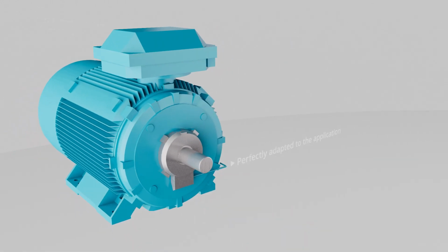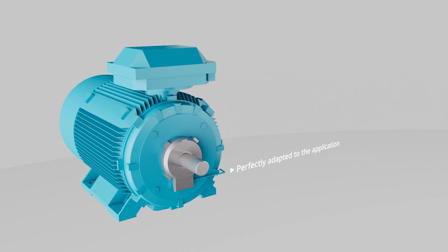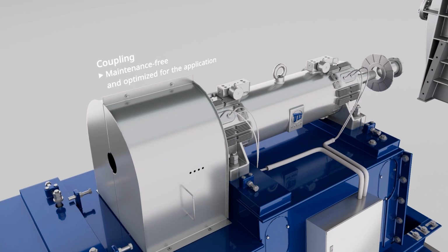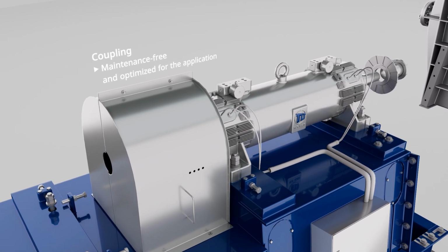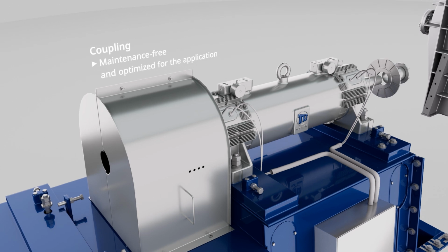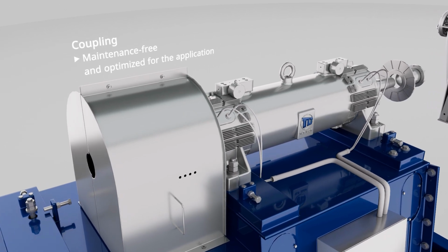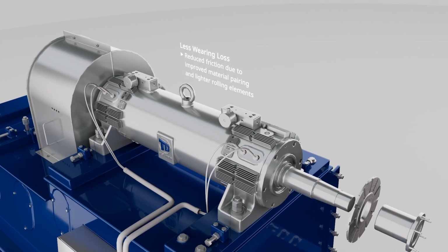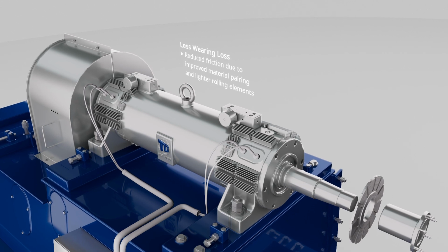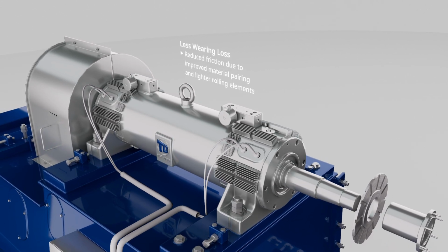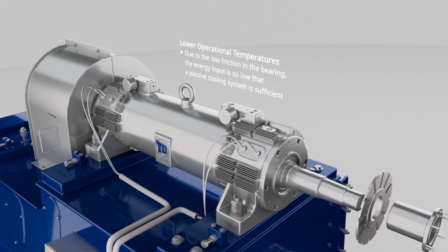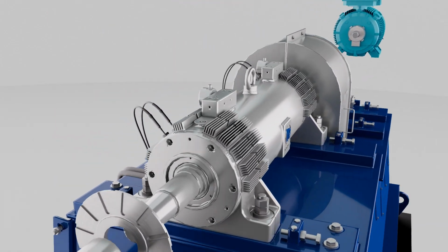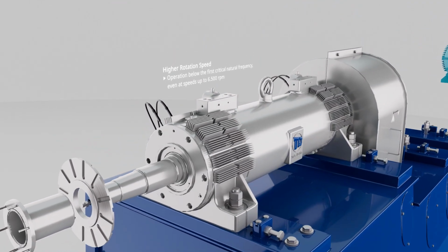One key component of the solution TLT Turbo developed is the practically maintenance-free bearing assembly. The assembly incorporates heavy-duty ceramic hybrid bearings, which has several benefits over conventional bearings in this application. Because this special material pairing of ceramic and steel undergoes less friction, heat development and wear in the bearing are reduced considerably. The result is a longer service life compared to conventional bearings. The bearing's high rigidity permits very high speeds during subcritical operation. This means that the fan does not have to pass through the first critical speed at startup.